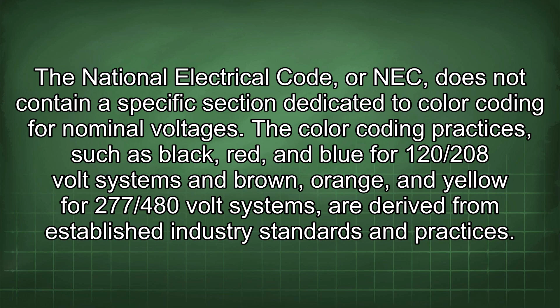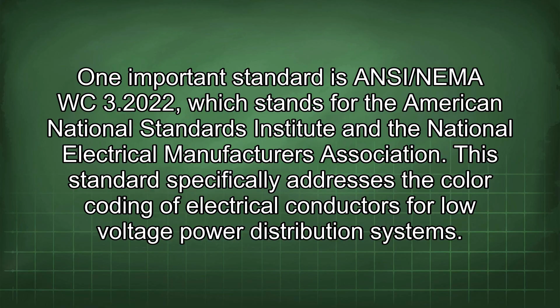One important standard is ANSI/NEMA WC 3.2022, which stands for the American National Standards Institute and the National Electrical Manufacturers Association. This standard specifically addresses the color coding of electrical conductors for low-voltage power distribution systems.